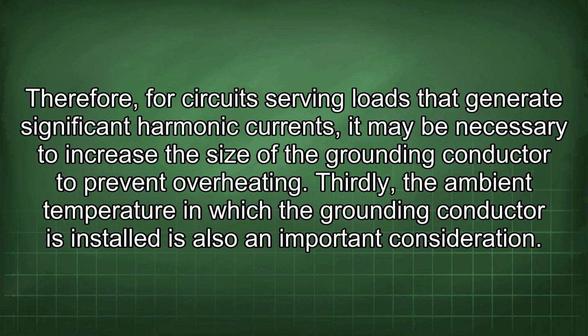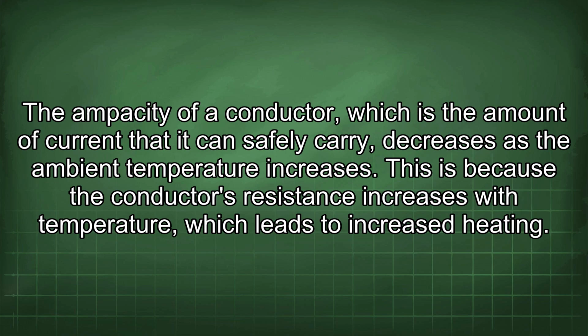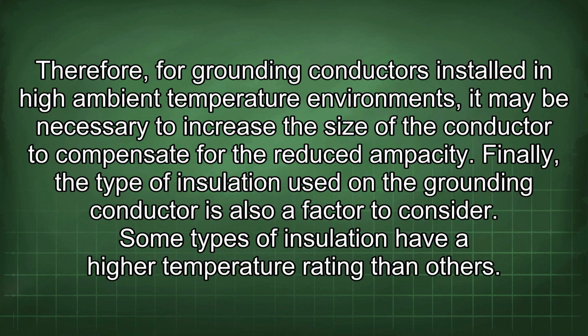Therefore, for circuits serving loads that generate significant harmonic currents, it may be necessary to increase the size of the grounding conductor to prevent overheating. Thirdly, the ambient temperature in which the grounding conductor is installed is also an important consideration. The ampacity of a conductor, which is the amount of current that it can safely carry, decreases as the ambient temperature increases. This is because the conductor's resistance increases with temperature, which leads to increased heating. Therefore, for grounding conductors installed in high ambient temperature environments, it may be necessary to increase the size of the conductor to compensate for the reduced ampacity.